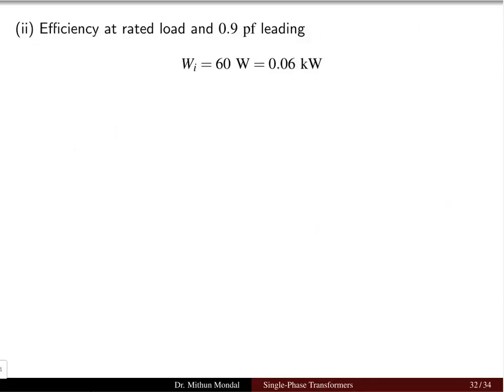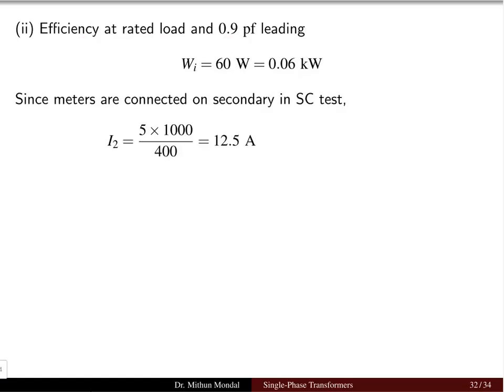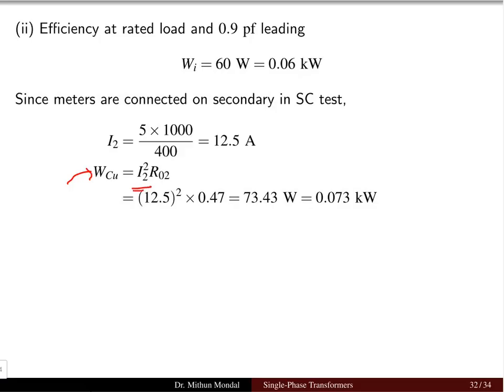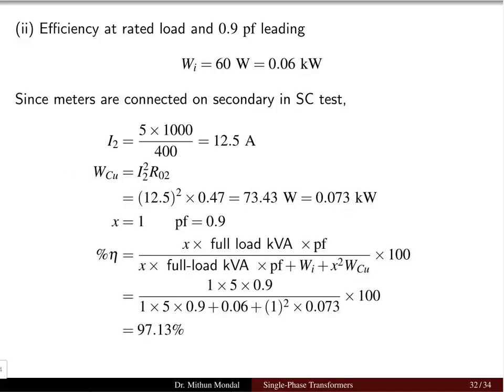Now, the efficiency we need to compute at rated load and 0.9 power factor leading condition. The iron loss is 60 watts, and the total current flowing on the secondary side is 12.5 amps, which we can compute. So the copper loss under the full load condition is I2 square into R02, which comes to 0.073 kilowatt. Hence, when the loading is full load and the power factor is 0.9, we can use the efficiency formula. Here x will be equal to 1, and the copper loss we have to compute at the loading condition. However, since the loading is full, we need not worry, we can directly substitute the value of the copper loss. So that is 97.13%.